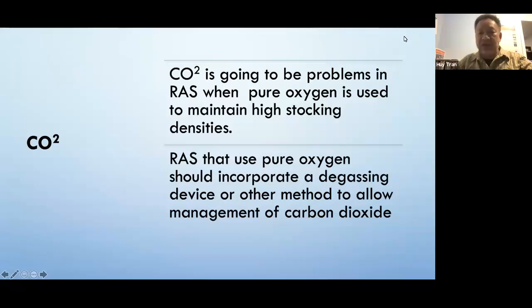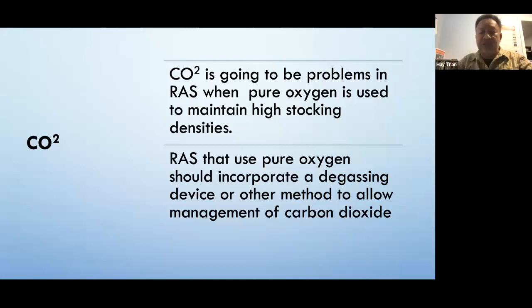CO2 will definitely be a problem in RAS when pure oxygen is used, due to the higher stocking density and metabolic rate. RAS systems using pure oxygen should incorporate a degassing device. Be aware that CO2 is a heavy gas — if you degas it but don't get it out of your building, it settles and can be re-absorbed into your system at a higher rate.